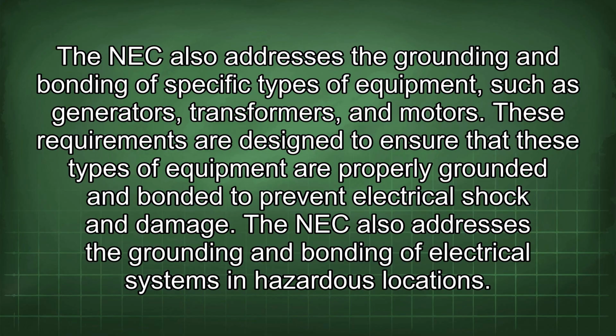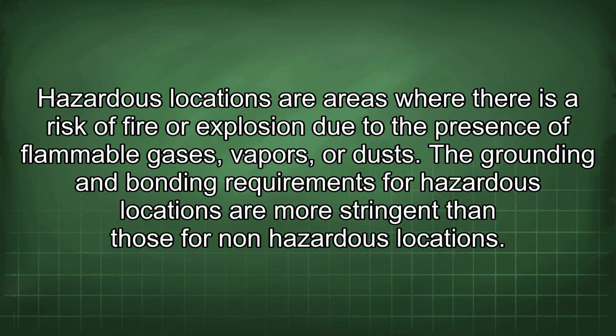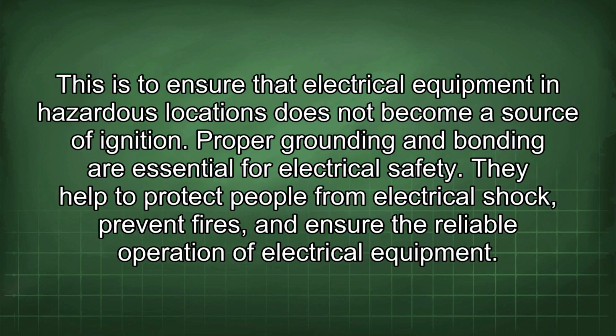electrical shock and damage. The NEC also addresses the grounding and bonding of electrical systems in hazardous locations. Hazardous locations are areas where there is a risk of fire or explosion due to the presence of flammable gases, vapors, or dusts. The grounding and bonding requirements for hazardous locations are more stringent than those for non-hazardous locations. This is to ensure that electrical equipment in hazardous locations does not become a source of ignition. Proper grounding and bonding are essential for electrical safety. They help to protect people from electrical shock, prevent fires, and ensure the reliable operation of electrical equipment.